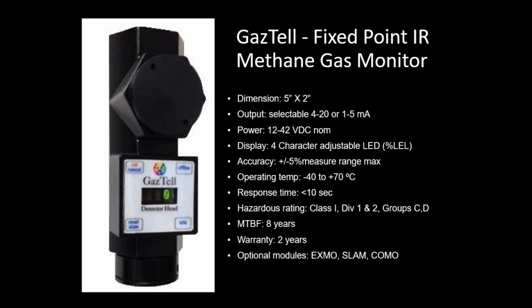Also, when you hook this up to a battery backup system, what we often found in the past is that when the batteries get to the end of their life, when the battery charging system turns on, they often don't create a good capacitor and allow the voltage to spike to 35 volts. On some of the older 24 volt or 12 volt systems, if your battery backup system spiked, you could easily blow out by a surge. You could blow out the detector head that's attached to that battery backup system. So now with a 12 to 42, if you do get a spike at 35 volts, we should have suppressed all the bad things that will happen when that does happen.